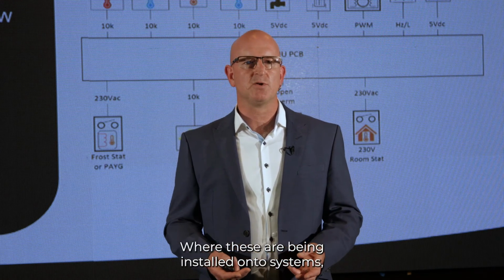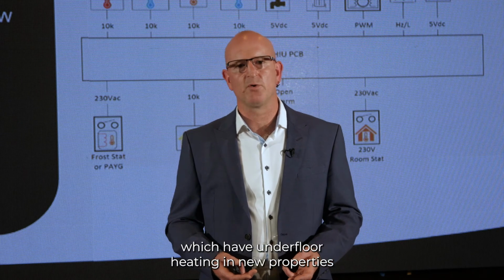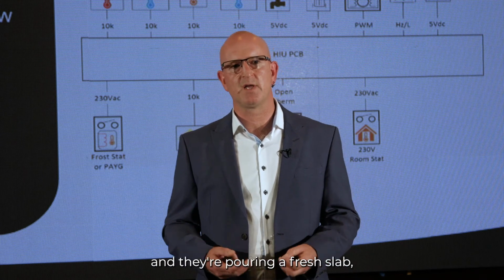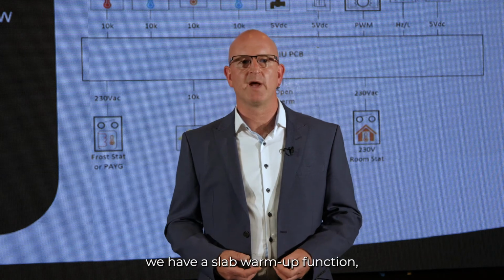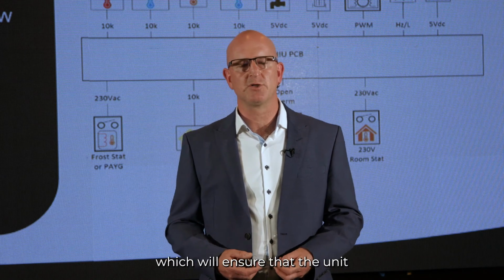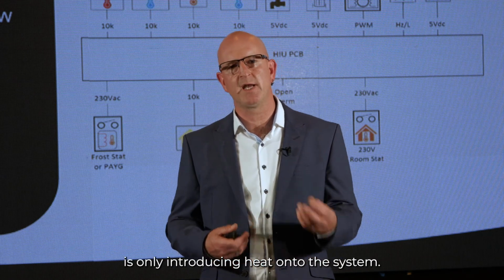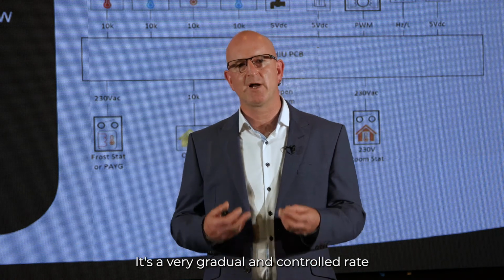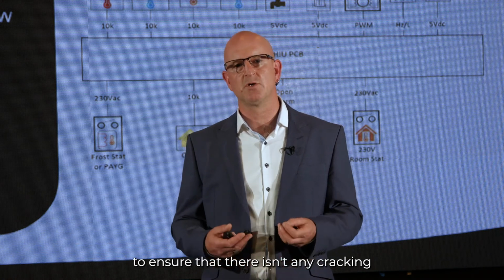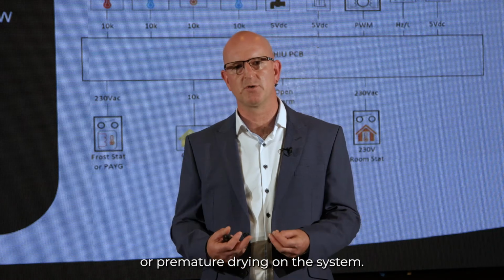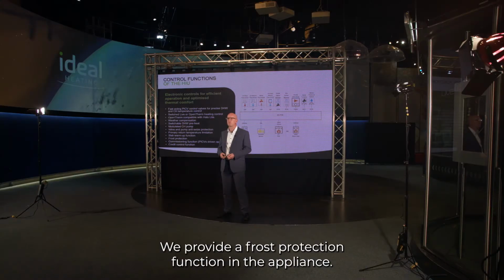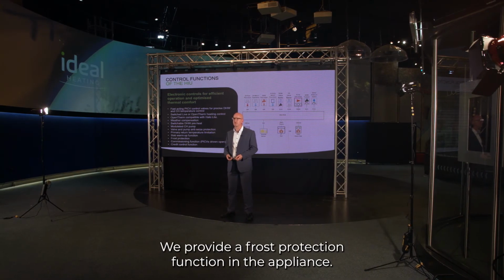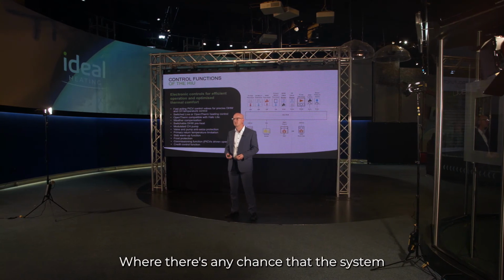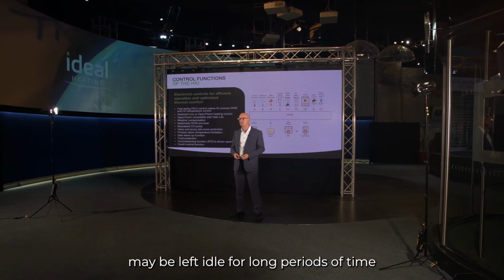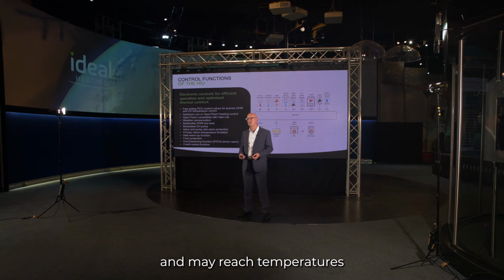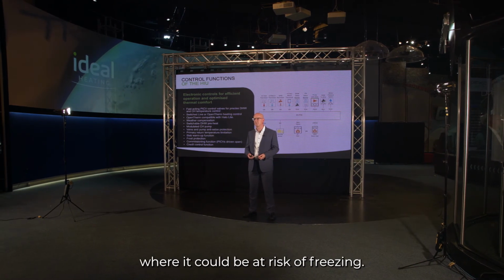Where these are being installed onto systems which have underfloor heating in new properties and they're pouring a fresh slab, we have a slab warm-up function which will ensure that the unit is only introducing heat onto the system at a very gradual and controlled rate to ensure that there isn't any cracking or premature drying on the system. We provide a frost protection function in the appliance where there's any chance that the system may be left idle for long periods of time and may reach temperatures where it could be at risk of freezing.